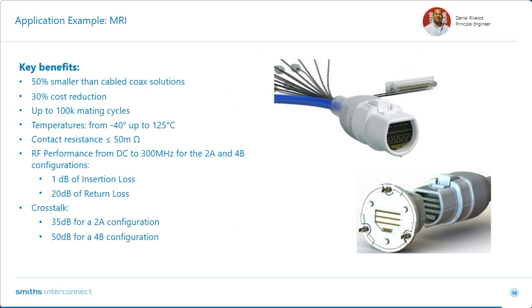For MRI applications, some of the key benefits are that it's 50% smaller than cable coax solutions, so reducing the size in operating rooms is huge, something very beneficial. There's a 30% cost reduction, up to 100K mating cycles, a temperature range from -40 to 125 C, and contact resistance less than 50 milliohms.